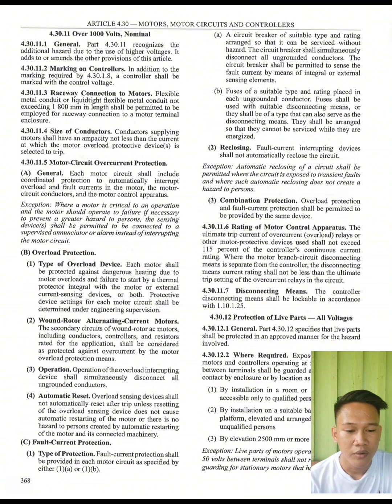Next, we have 4.30.11.6 Rating of motor control apparatus. The ultimate trip current of overcurrent or overload relays or other motor protective device used shall not exceed 115% of the controller's continuous current rating. Where the motor branch circuit disconnecting means is separate from the controller, the disconnecting means current rating shall not be less than the ultimate trip setting of the overcurrent relays in the circuit.